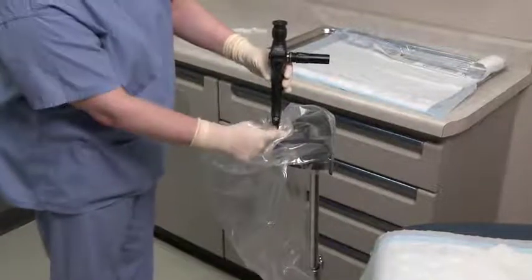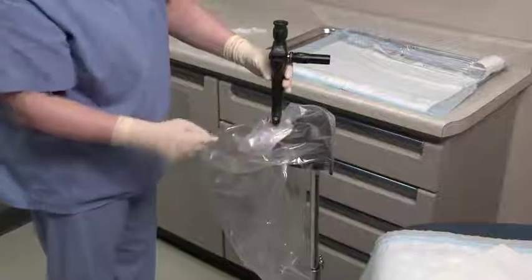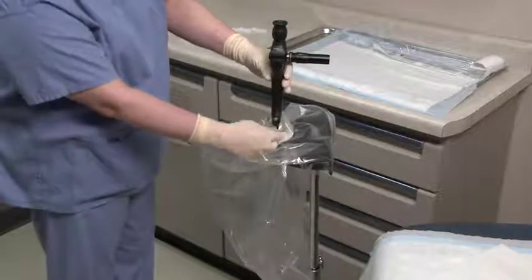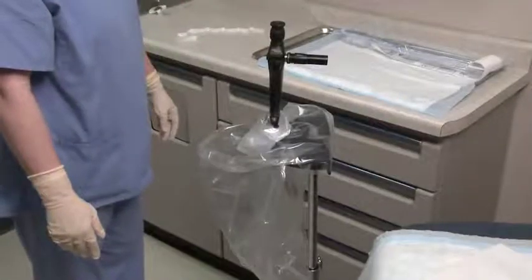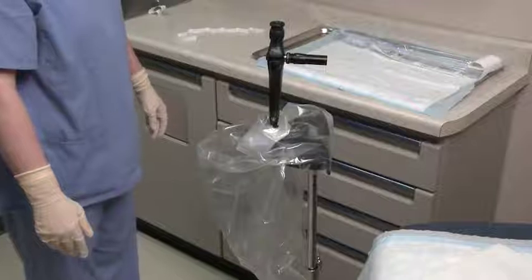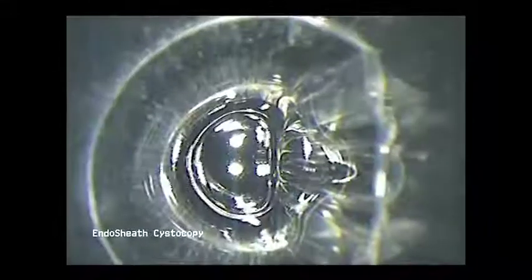Align the locking knob on the cystoscope with the vertical slot on the sheath connector. When the locking knob is fully seated in the slot, rotate it to a horizontal position. This secures the fit between the sheath and the cystoscope. You can verify proper seating of the cystoscope distal head into the sheath window by visualizing a clear image through the cystoscope with a light source on.